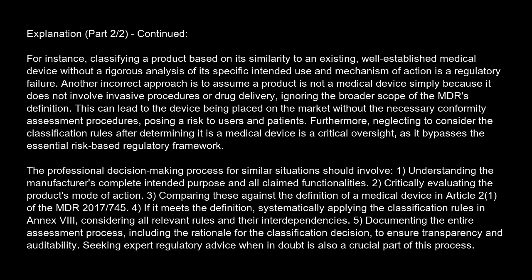If it meets the definition, systematically applying the classification rules in Annex VIII, considering all relevant rules and their interdependencies. 5. Documenting the entire assessment process, including the rationale for the classification decision, to ensure transparency and auditability. Seeking expert regulatory advice, when in doubt, is also a crucial part of this process.